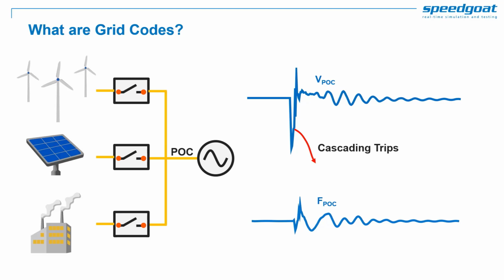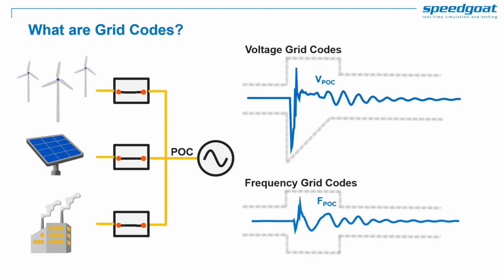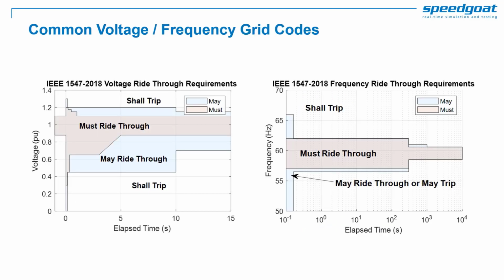Grid codes add a boundary to such scenarios. For example, in cases where the grid voltage drops, you have standards defining if the device must stay connected to the grid or when it must trip. Similar codes also apply in the frequency domain. Let's look at grid codes commonly used in the US. For example, we consider the IEEE 1547 grid code, typically used for distributed energy systems. We have a voltage ride-through and a frequency ride-through code. For the voltage ride-through, the grid code defines that for a short voltage drop, the device must ride through. For a longer or stronger voltage drop, it may ride through, but for an even longer or stronger voltage drop, the device must trip.